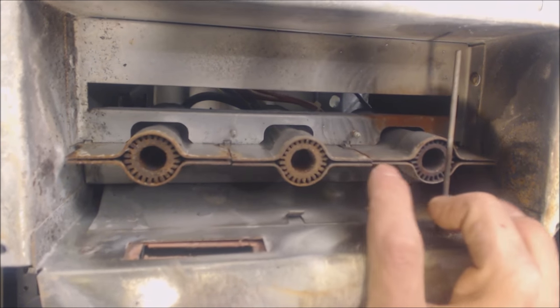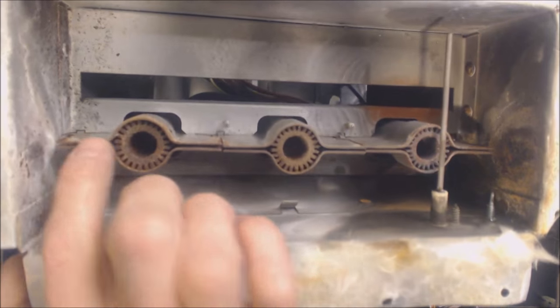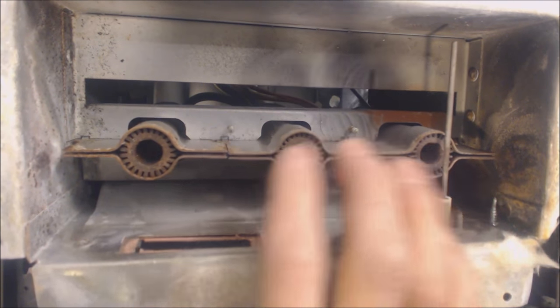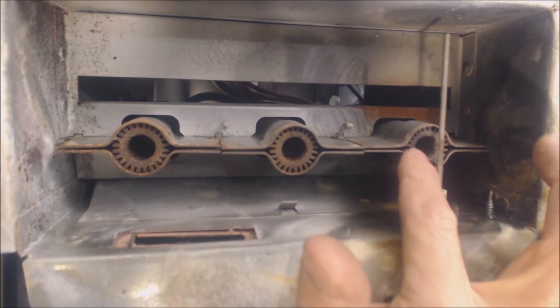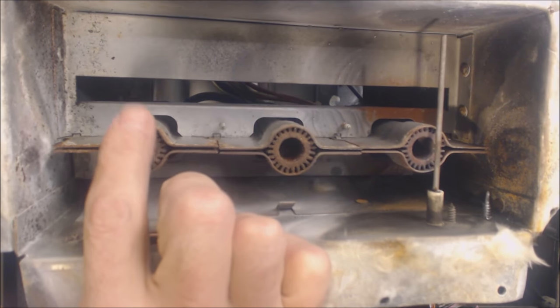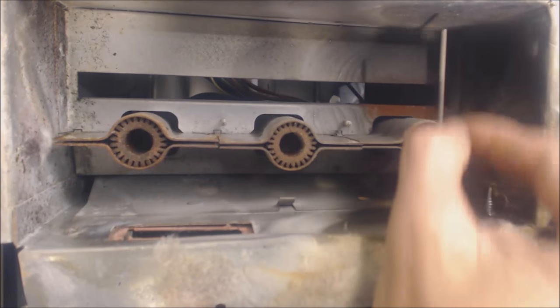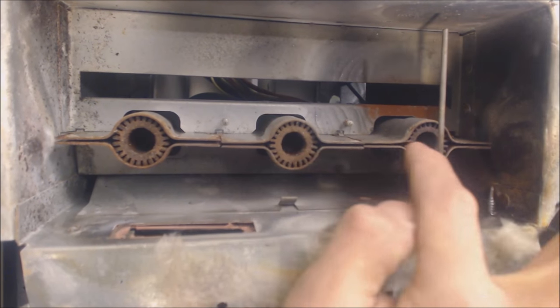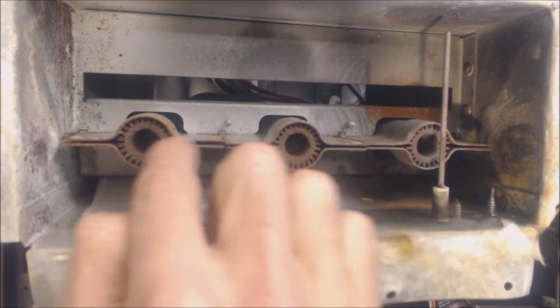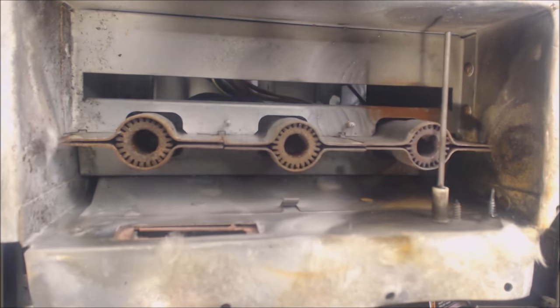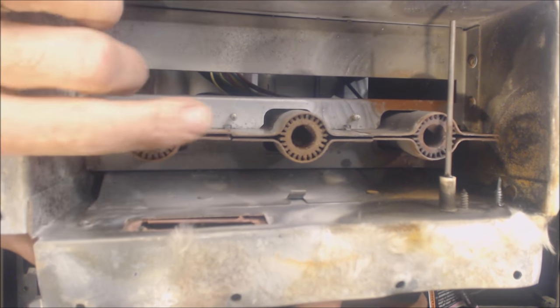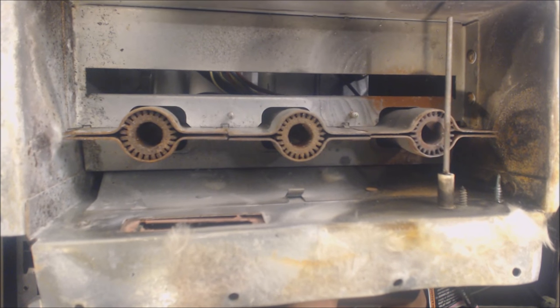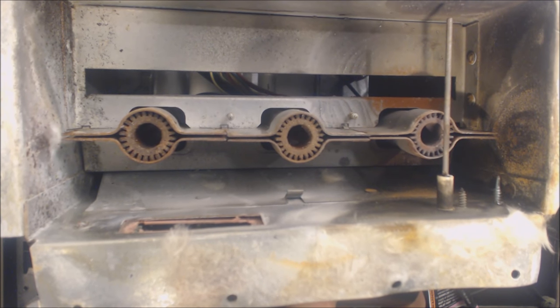And then this would light right along here and then this would light. And basically you've proven that all of the burners between here and here have lit by having the hot surface igniter or a spark ignition here and the flame rod sensing the flame over here, because there's no way for the flame to have got over here except for by through all of the other burners that you could have up to six, say six on a residential light commercial heater.